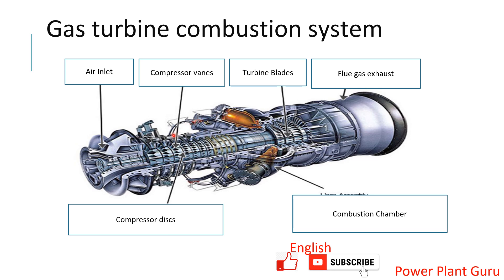There are a number of components in these combustion chambers — like liquid fuel tubing, fuel nozzles, and crossfire tubes connecting the combustion cans. If any of these components have a problem, there is a possibility of higher fuel flow going into one combustion chamber or less fuel going into another. There is a small allowance for minor unevenness, but if the temperature unevenness is high, you will have a serious problem — not immediately, but in the long term.